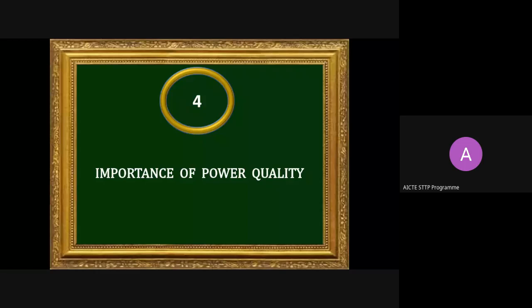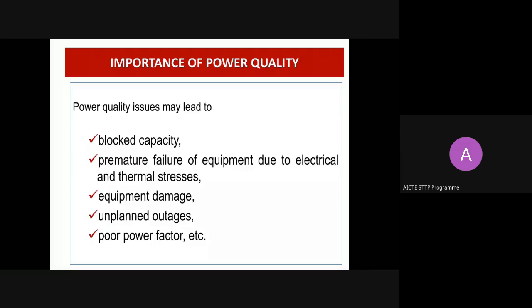Here, first, the blocked capacity. What does it mean? Because of the presence of poor quality of the voltage or poor quality of the current, harmonic distortions in the current and harmonic distortion in the voltage, your conductor may not be in a position to carry the current it was designed for. We have to underutilize the capacity. That's why it creates blocks to the total capacity.